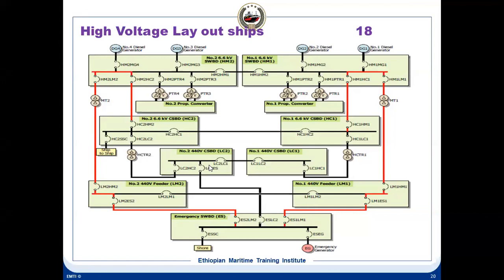So generally, high voltage equipment means starting from the generation: generator, main switchboard, transformers, they are all high voltage. Now here you can see the two propulsion converters, which use a high voltage transformer. Two transformers are there here. Here also two transformers. The primary is delta, the secondary is star delta here. Here also primary and secondary star delta. So these are all high voltage equipment. Low voltage is only this switchboard and this switchboard. These three switchboards are low voltage, the remaining are high voltage.